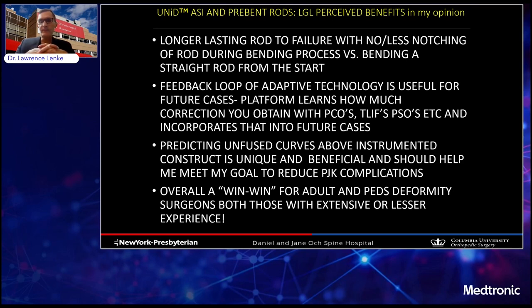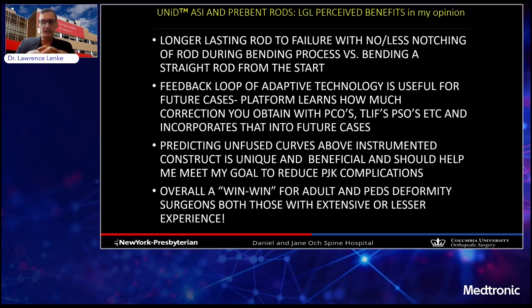The feedback loop of this adaptive technology is useful for your future cases. The platform learns how much correction you obtain with various maneuvers — PCOs, TLIFs, PSOs, etc. — and incorporates that into future cases for better prediction of what you'll achieve. Predicting the unfused curves above the instrumented construct is very unique and beneficial and should help meet our goals to reduce PJK complications. Overall, this is really a win-win technology for adult and pediatric deformity surgery for surgeons with extensive or lesser experience.